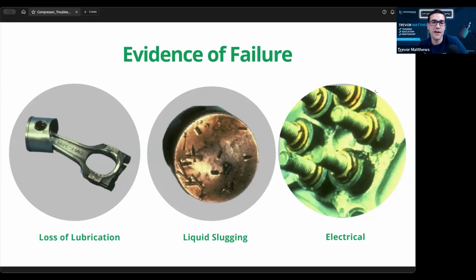You don't just turn the switch on and hope that it's going to run totally fine. You've got to have your electrical meter there. You've got to have your gauge on, because if you turn that switch on and all of a sudden your discharge is not going up and your suction's not going down and they're staying even, you're probably going to rewire it, right? Just switch one of those legs. And eventually you'll be on screw compressors, and screw compressors have got to go one direction, or they will certainly wash themselves out, because a lot of them don't even have oil pumps. Some of them don't have oil pumps. They're all pressure fed oil. So you want to make sure it's going in the right direction.